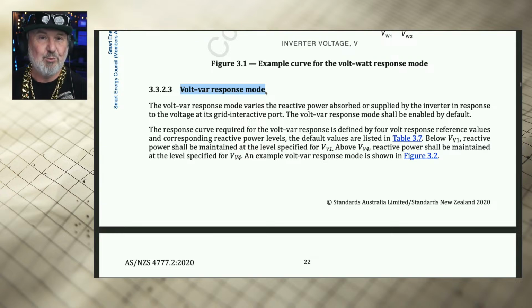That turned out to be a really bad thing, because every inverter connected to the national grid, whether in Australia or New Zealand, is generating at basically the same time since they're synchronized with the sun. That means if the volts go up to a certain level, they could all switch off together - giving you a massive power reduction all at once, in a very short cascade over a few seconds of inverters turning off.